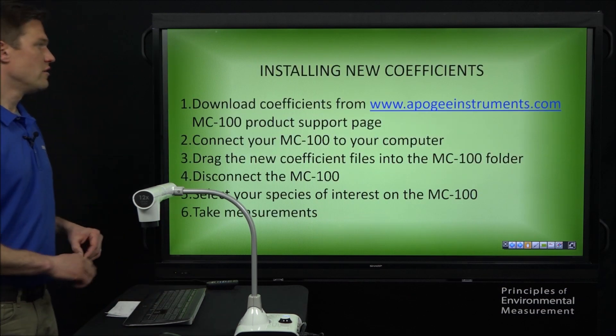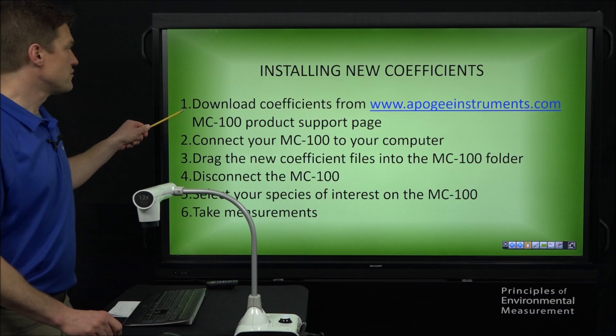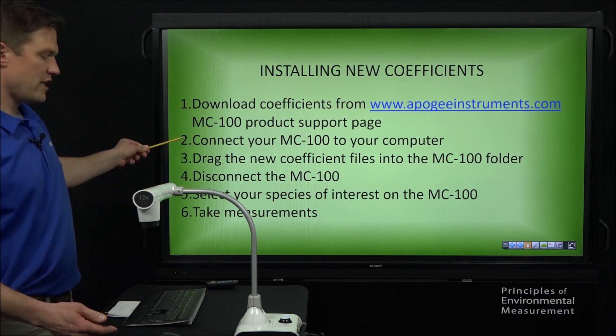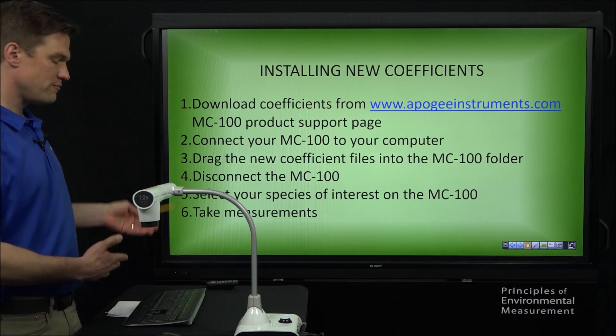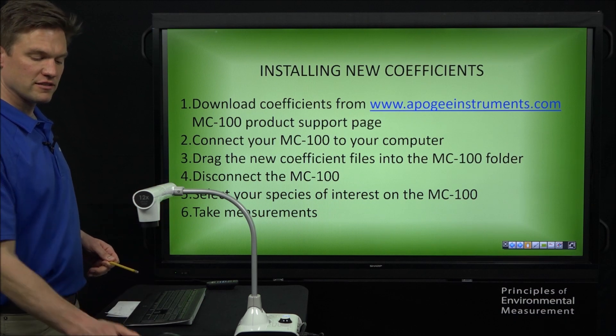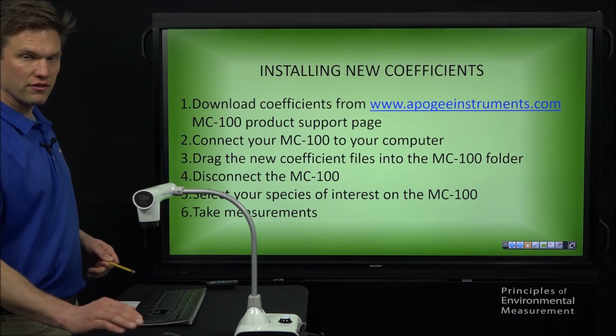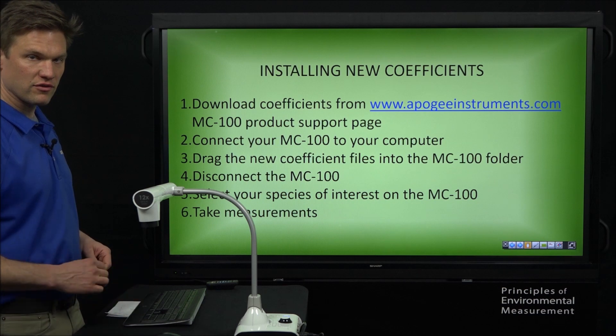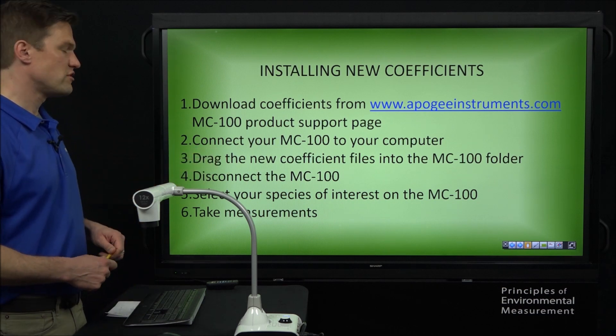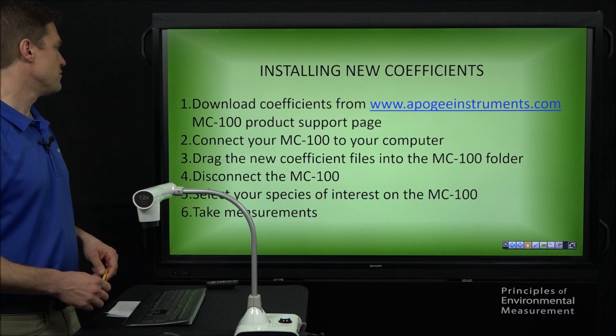So, the process will be, we go to our website and we download the files from the MC100 product support page. We connect this MC100 to the computer and that will allow us to access the folder on this device with the files.